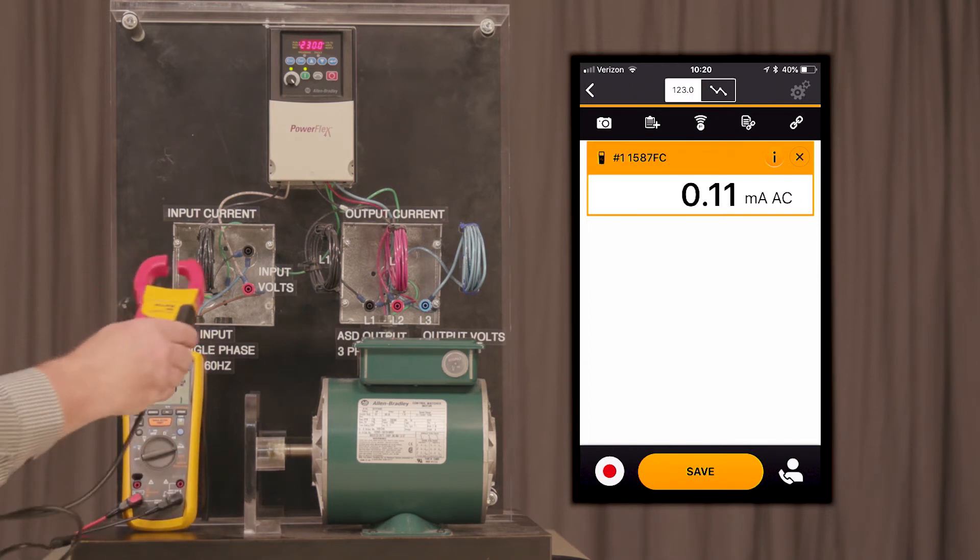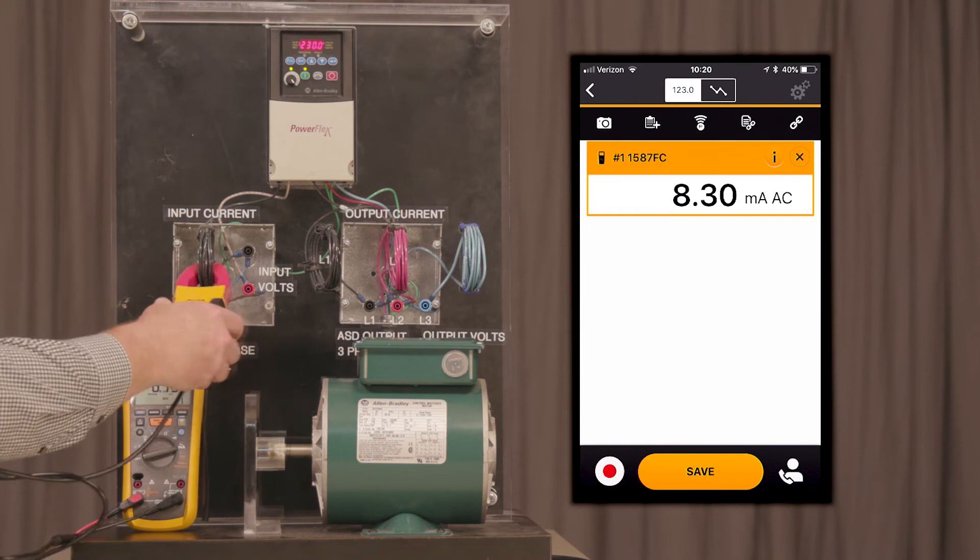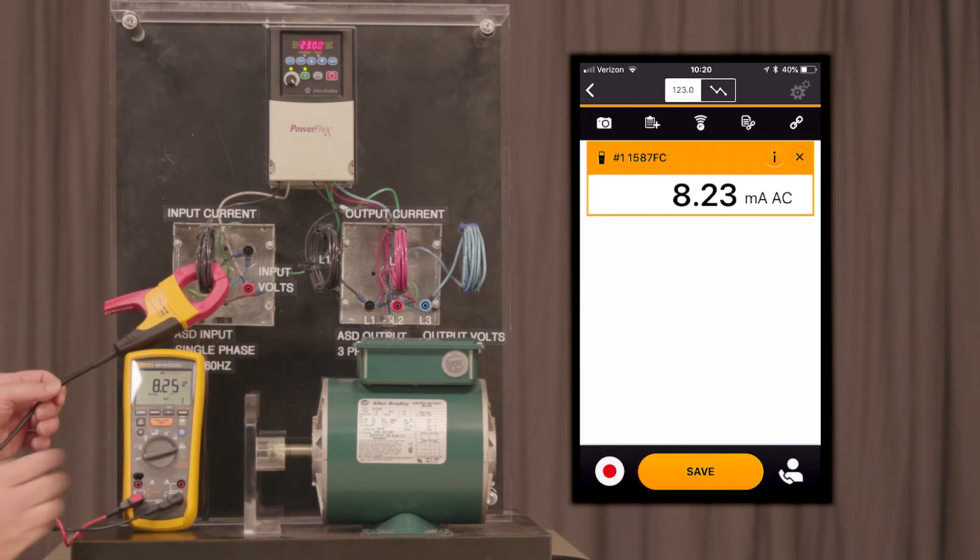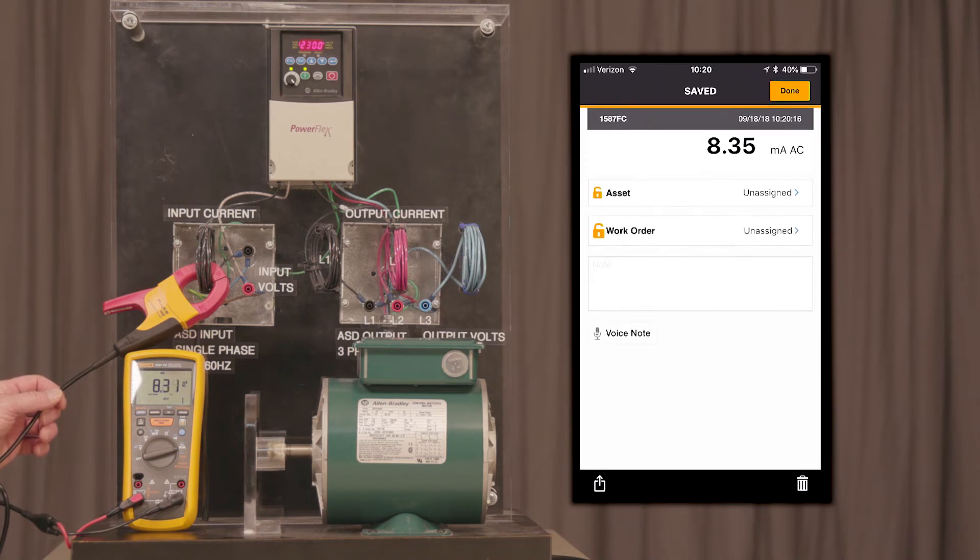Let's go ahead and make a current input measurement on the input to the VFD drive. As you can see here, I'm getting 8.3 milliamps. We're going to go ahead and save this measurement.